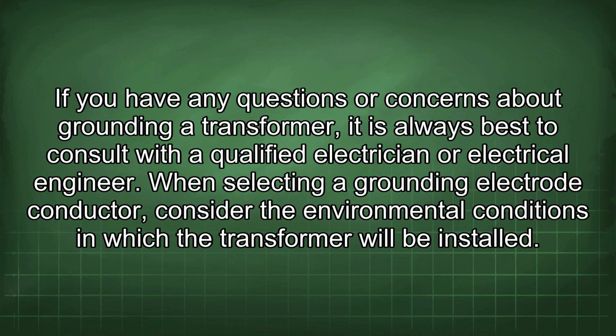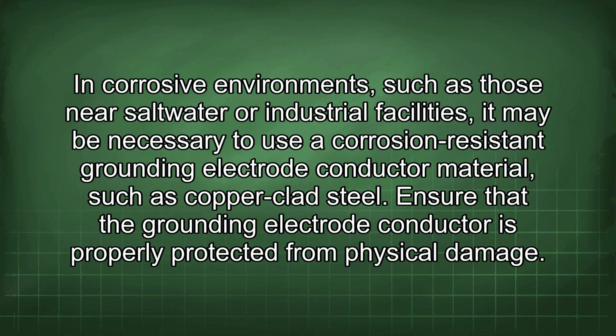If you have any questions or concerns about grounding a transformer, it is always best to consult with a qualified electrician or electrical engineer. When selecting a grounding electrode conductor, consider the environmental conditions in which the transformer will be installed. In corrosive environments, such as those near saltwater or industrial facilities, it may be necessary to use a corrosion-resistant grounding electrode conductor material, such as copper-clad steel.